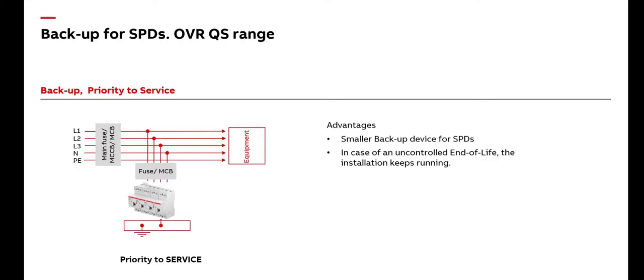Okay. If instead your main concern is to avoid as much as possible any interruption of service, in this case you had better invest in a dedicated backup device for the SPD, correct? Correct. In this case, the advantage is that in the case of an uncontrolled end of life, your installation will continue to be fed. The risk, however, is that the backup device trips in case of an uncontrolled end of life, nobody notices it for a certain period of time, and during this time, your installation will keep working unprotected.